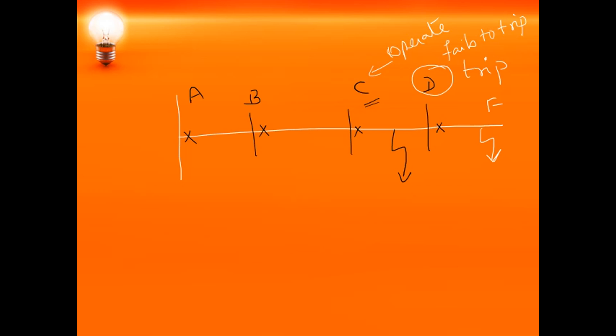In case the circuit breaker at C fails to operate, then the circuit breaker at B has to operate, which acts as a backup. The relay which is used has to identify in which location the fault is, and accordingly that particular circuit breaker has to operate. So the relay should have proper selectivity. To have proper selectivity, there are three protective schemes which can be used depending upon the system condition.